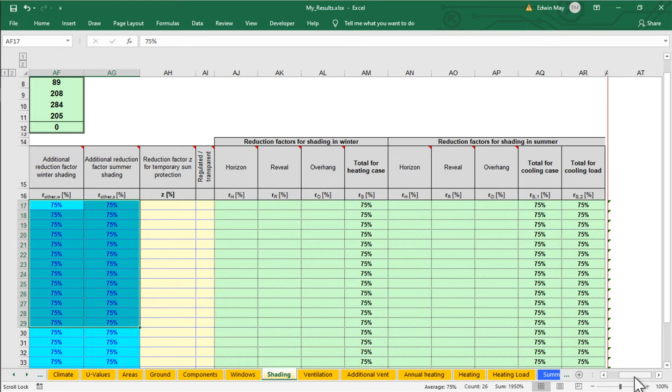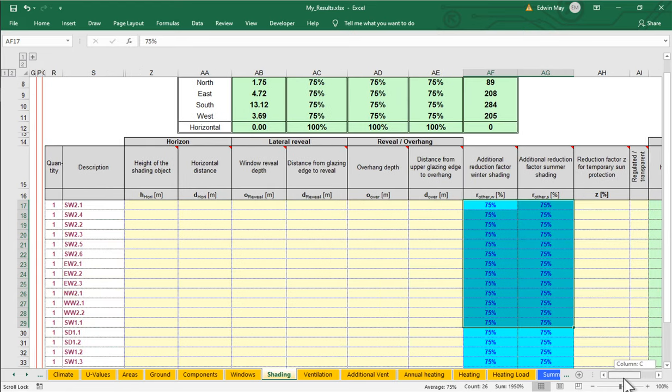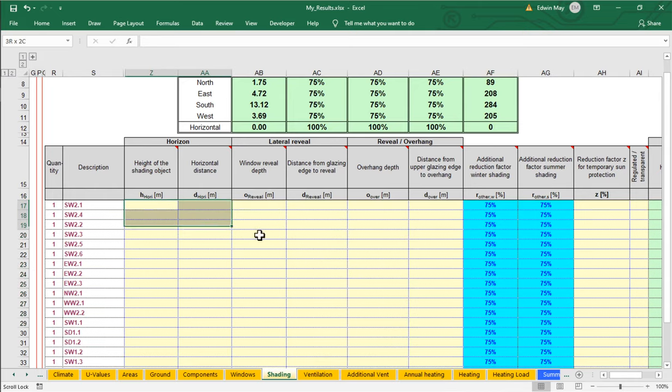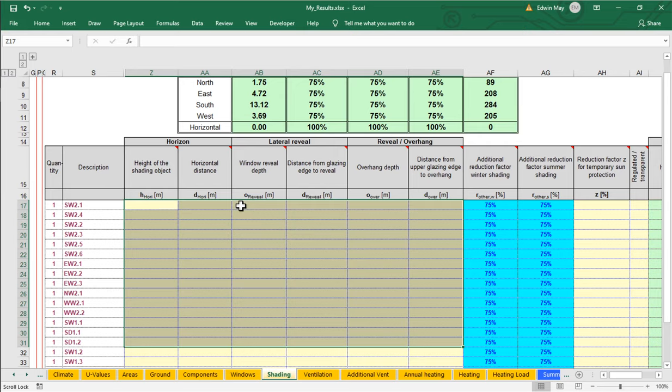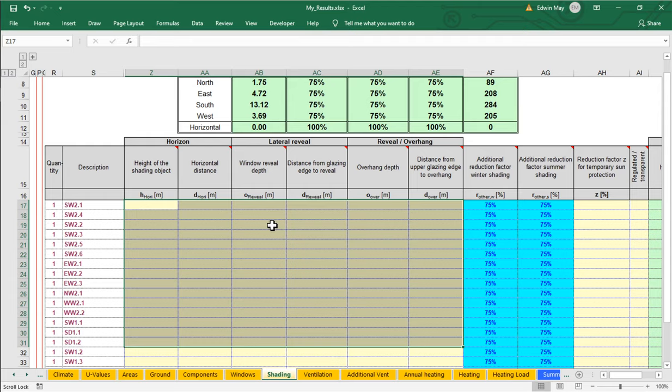So that's how everything is set up by default. So in order to calculate these shading factors more accurately, what we actually need to do is fill in all of this information right here. We have to go through, and one window at a time, we have to find any horizon shading objects. We have to find any side reveal shading objects. We have to find any overhead or overhang shading objects. We need to calculate the distances out from the glazing, the plane of the glass out to those objects, and then input all of that information here one data point at a time.